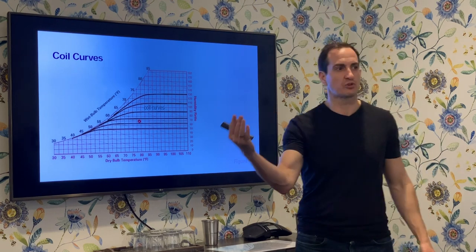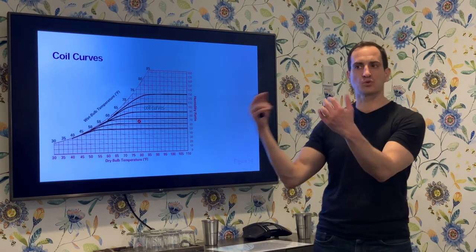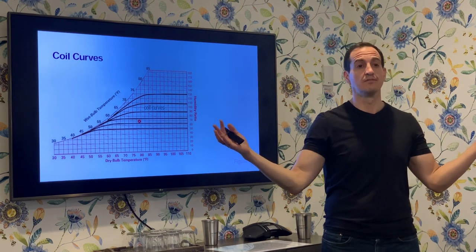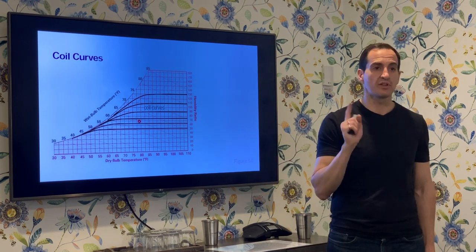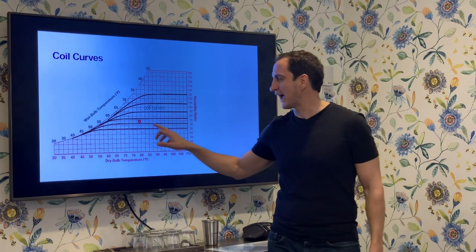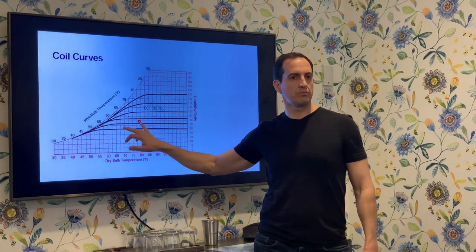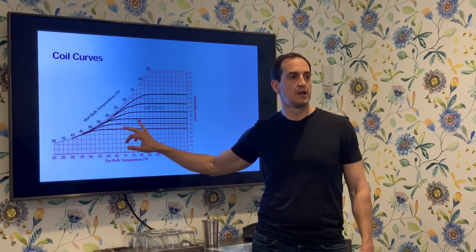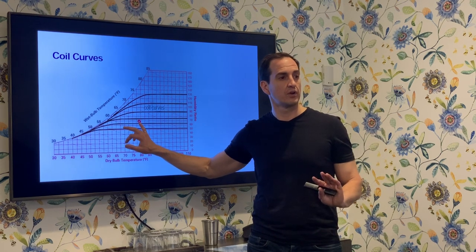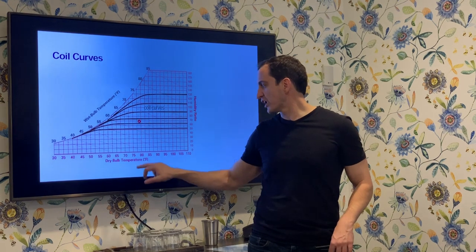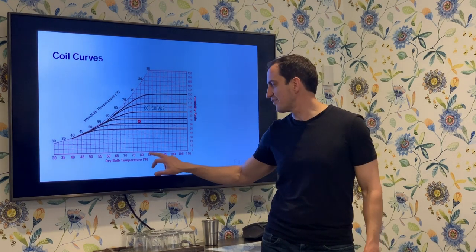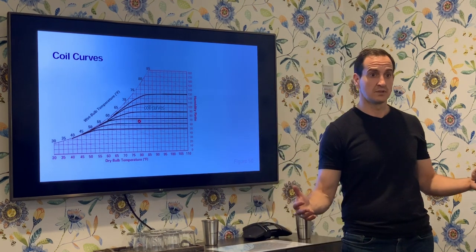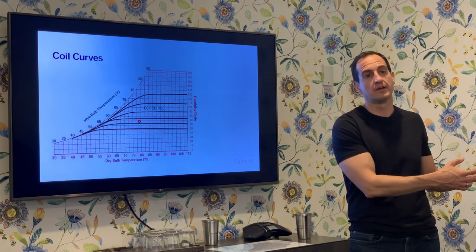The reheat is free in the sense that we were going to run the compressors anyway — we're not adding electric resistance heaters or gas burners. We're using the compressor energy we'd send to the environment anyway for reheat. However, traditional reheat systems can only reheat to about 10°F below the starting condition. There are conditions we'll discuss in later parts of this series where we need air at 85 or even 90°F — not just 68 or 75°F — to keep the room at the same temperature, VPD, and everything else needed to maintain a consistent plant environment and maximum vitality.